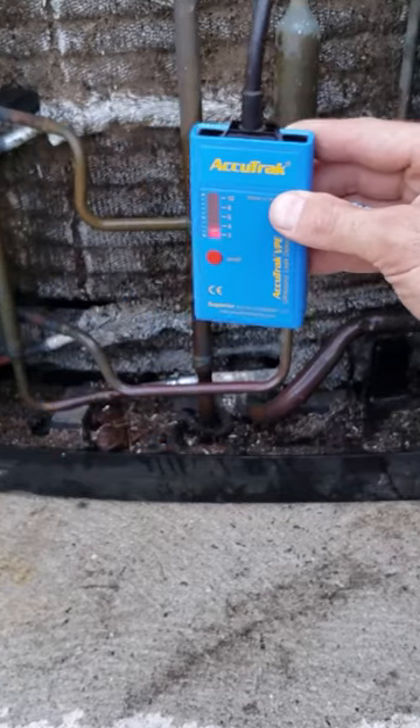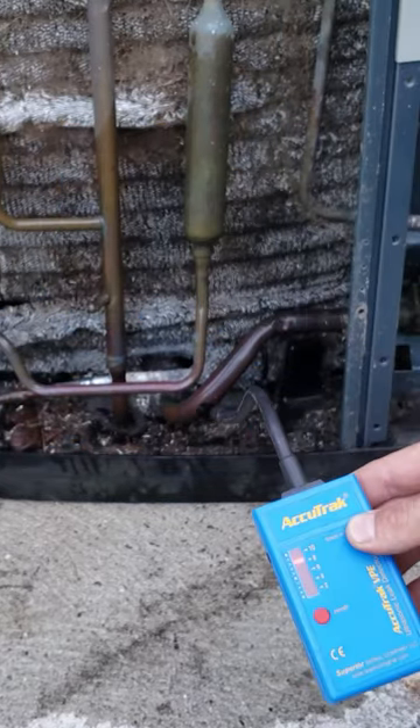We can use an AccuTrak ultrasonic leak detector in order to search for refrigerant leaks on air conditioning and heat pumps. Once we target it and find our leak, we're going to then put anti-corrosive bubble leak detector on to see the bubbles forming.